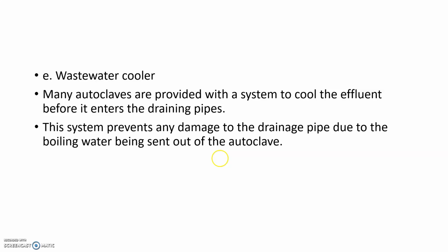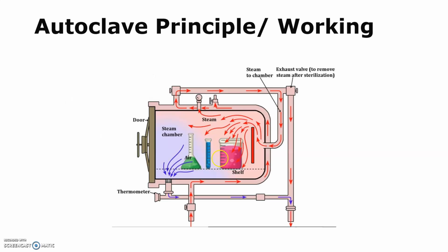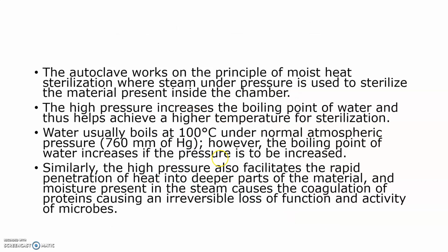Many autoclaves are provided with a system to cool the effluent before it enters the draining pipes. This system prevents any damage to the drainage pipe due to the boiling water being sent out of the autoclave. This is the picture of an autoclave. Now coming to the principle and working of autoclave.